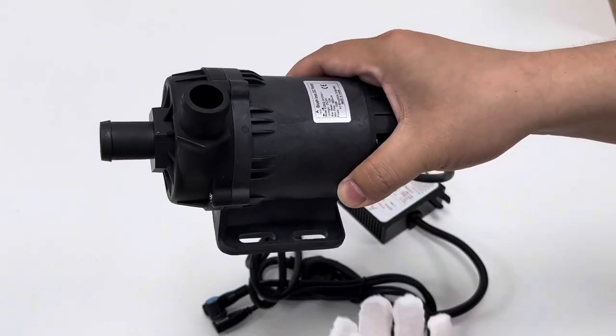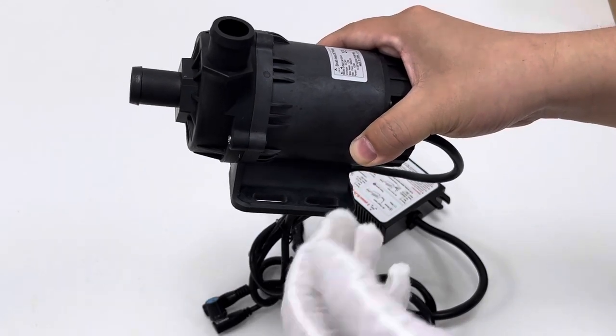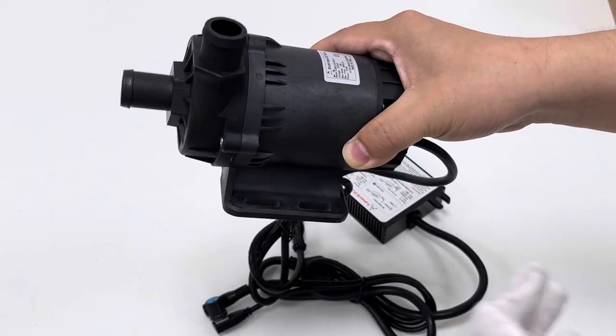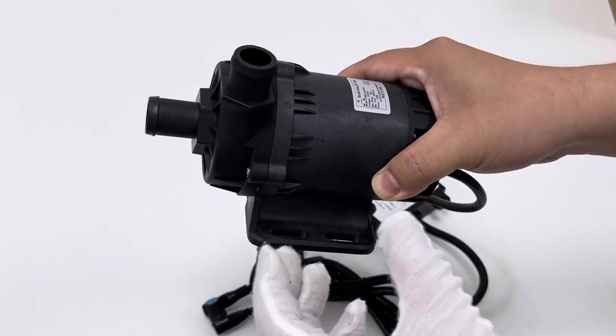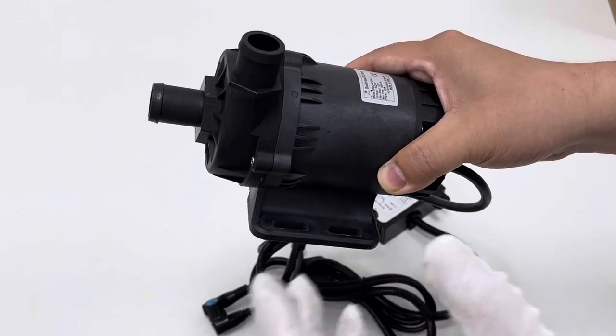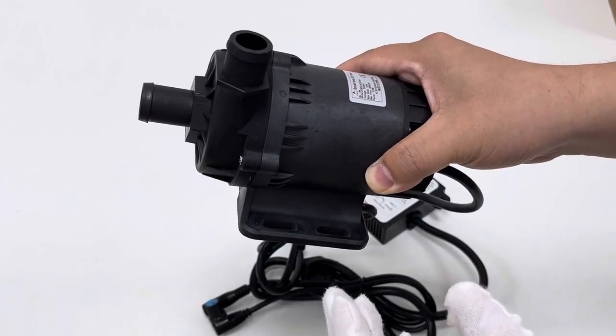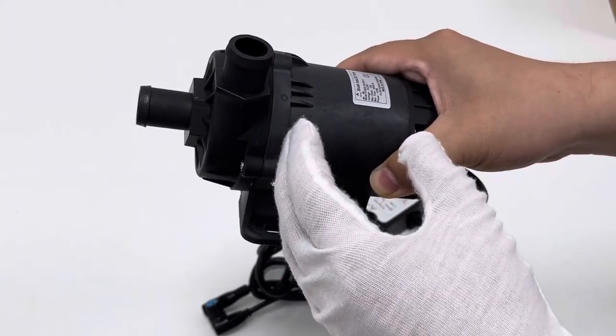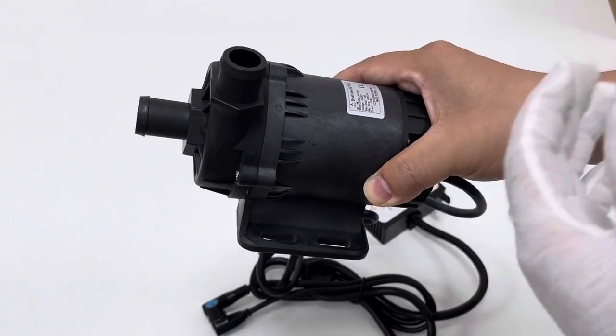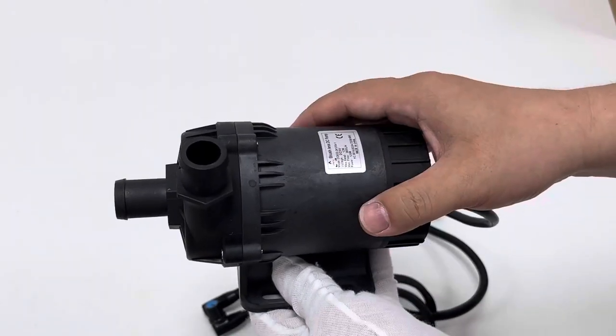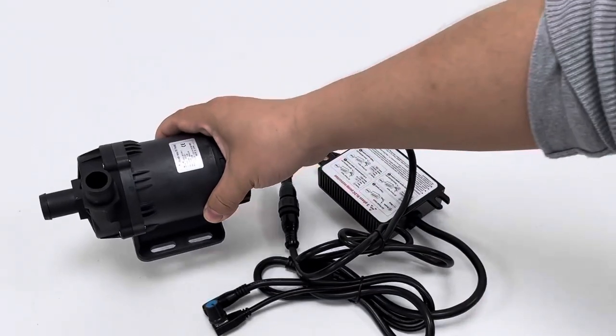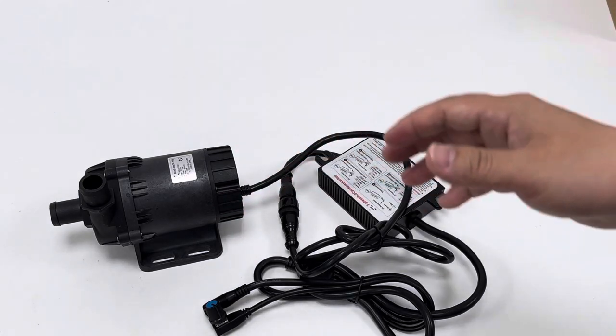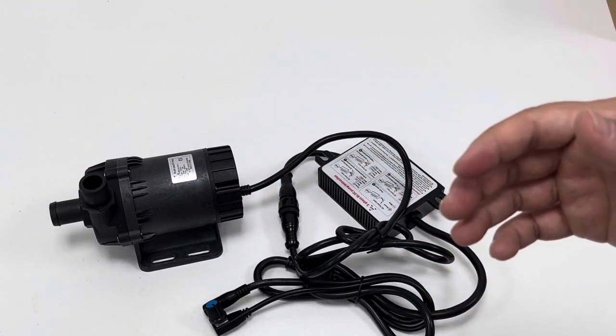And the other good feature is that this pump is equipped with the constant power design when it is over-voltage. For example, when the powering voltage exceeds 24V DC but still within reasonable range, for example, 28V DC within 24 to 28 range, this pump's power level will be kept identical without rising along with the powering voltage. So that the inner working circuit will be kept in a reliable environment. A very good feature for the power supply with not so reliable or stable output voltage.